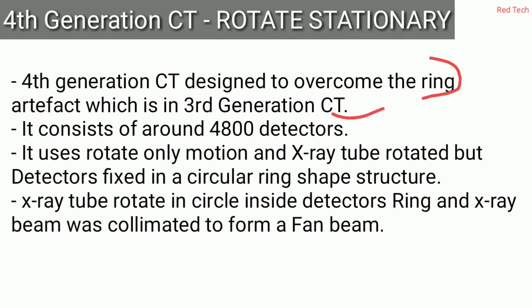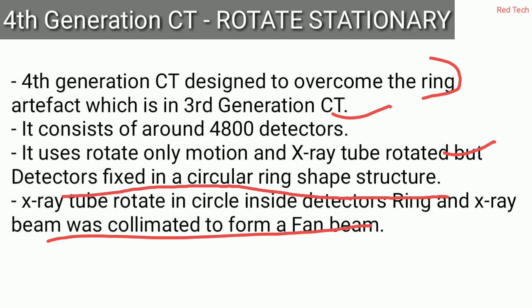In the fourth generation CT, a huge number of detectors were used — more than third generation. Specifically, 4800 detectors were used. It uses rotate-only motion: the X-ray tube rotates, but all the detectors are fixed in a circular ring shape. The X-ray beam is collimated to form a fan beam.